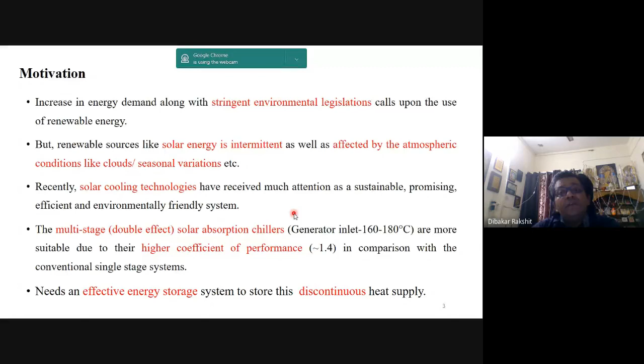I discussed a bit about how this absorption chiller works. It has two sides, the absorber side and the condenser side. On the condenser side there is charging, and on the absorber side there is discharging. But our whole aim is not to concentrate on the absorption chiller itself. The aim is how to design this thermal energy storage system so we can perennially get hot water maintained at 180 degrees centigrade, achieving a higher coefficient of performance of around 1.5. With that, this entire project was envisaged.